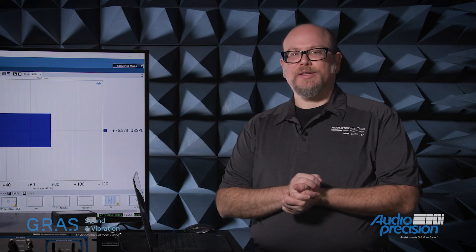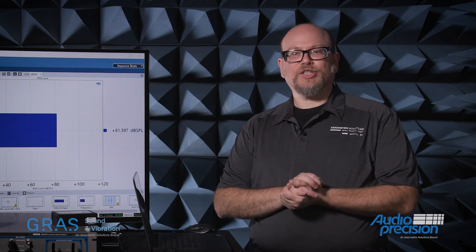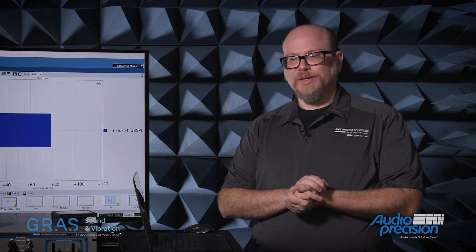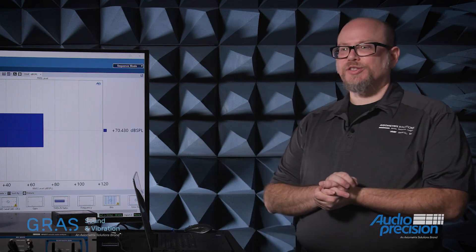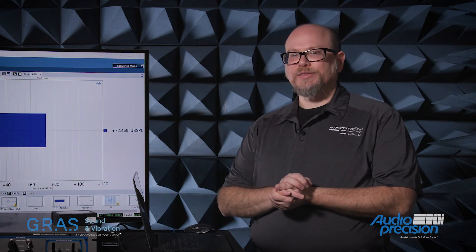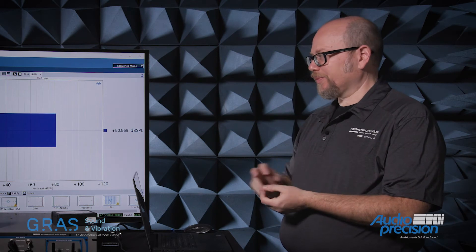The next step, which is what I'd like to demonstrate today, is SysCheck 2. What SysCheck 2 allows us to do is actively verify that the sensitivity of the microphone has not drifted since it was last calibrated.